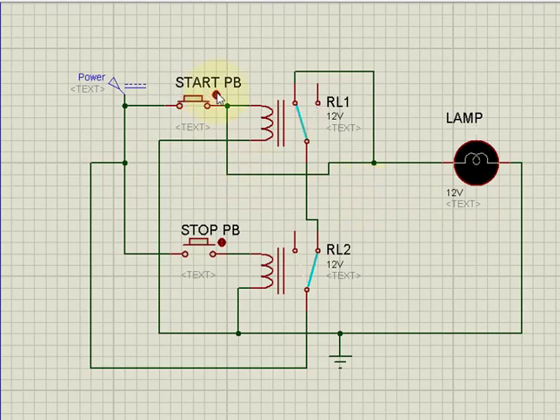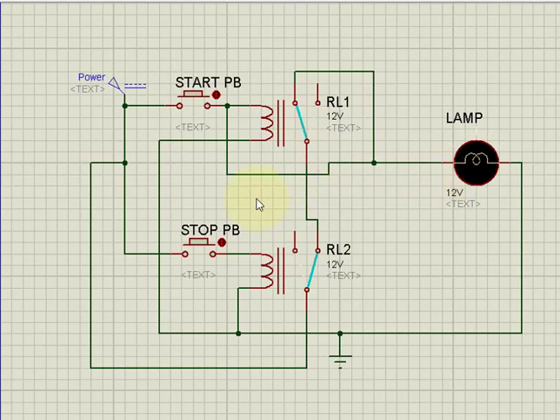If I release the stop button, the lamp remains in the off state unless I press the start button again. So: press start — lamp on; press stop — lamp off immediately. This confirms the relay latching circuit works as required.